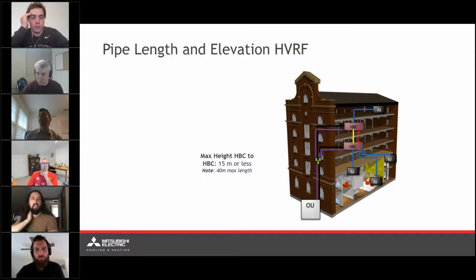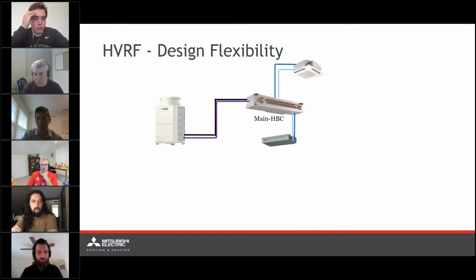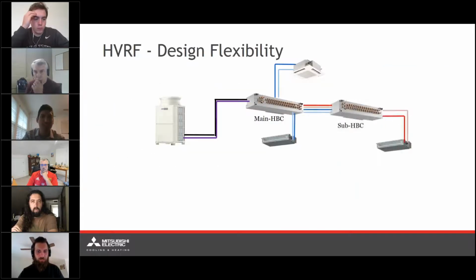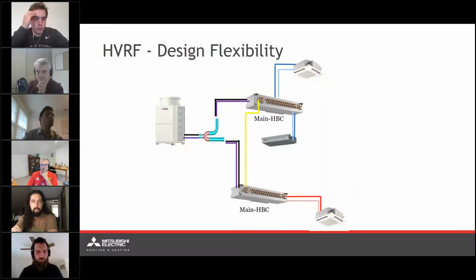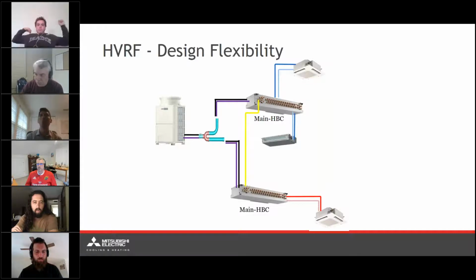Yes, so for initial launch for the HVRF system, when it's first coming out in the US, we're only going to be talking about our concealed ducted units. In this particular circumstance, we're looking at cassettes attached. Those are going to be a future addition, but for the time being, we're only going to be talking about these ducted units right here that are going to be attached. That's because we need to rework the actual fan coils themselves. Again, we're not going to have any of the valves in the actual fan coils themselves, so we need to rework the interior of each. So for the time being, we're only going to be looking at the medium static pressure concealed ducted units.